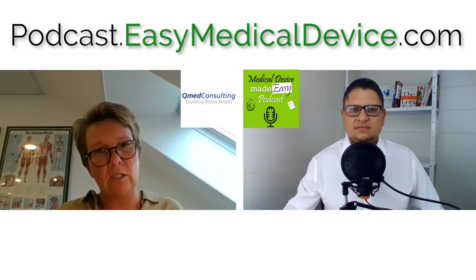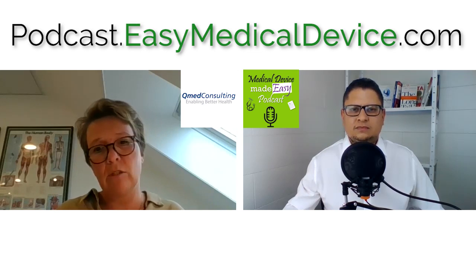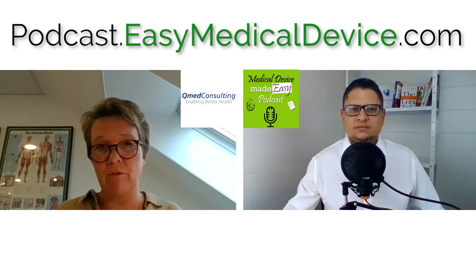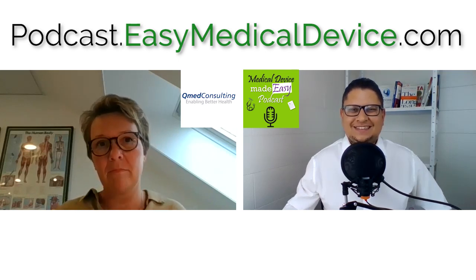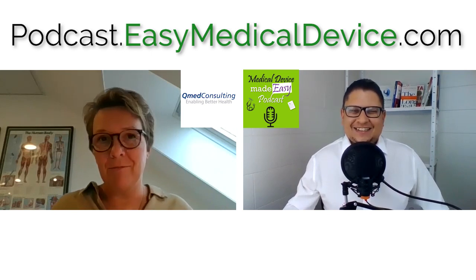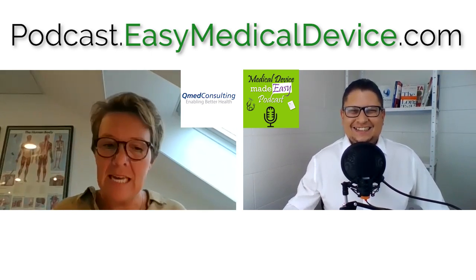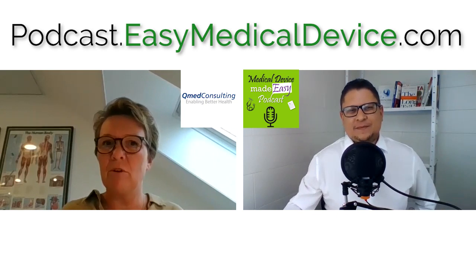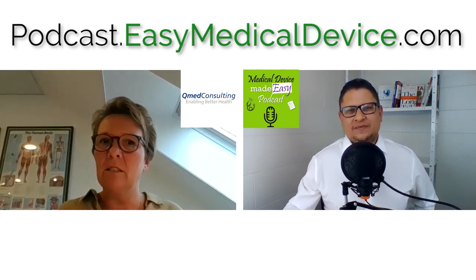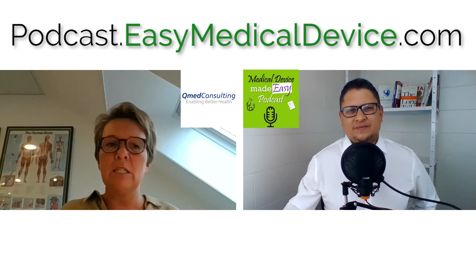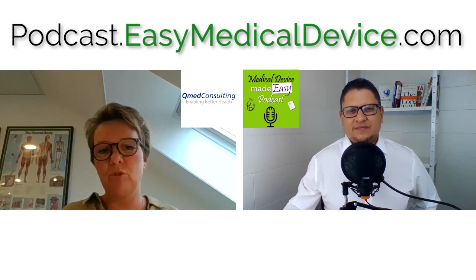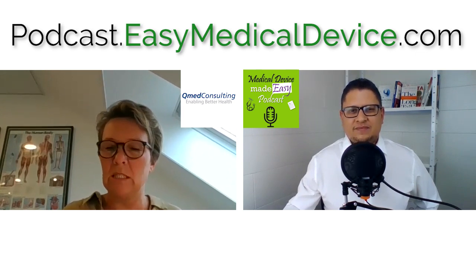And sufficient quality, when I listen to how Qmed interpreted it, is basically that you have to follow 14155. Okay. So it's easy, right? It's not easy, but if you follow the recipe for a good clinical trial, and you have a statistical rationale, you cover your claims with the patient groups and the indications and all these things, then it's sufficient clinical evidence, and you can use these data to support your CE mark under the MDR.